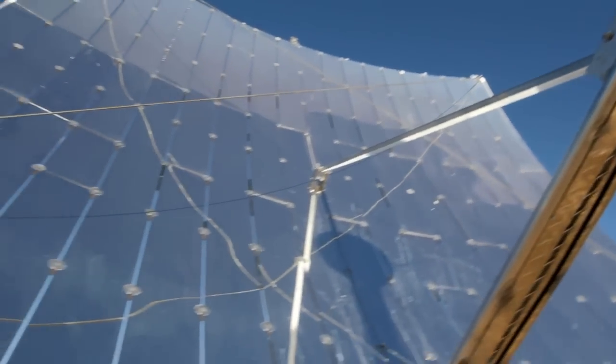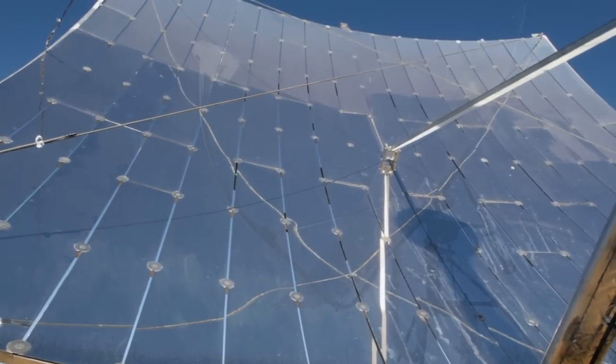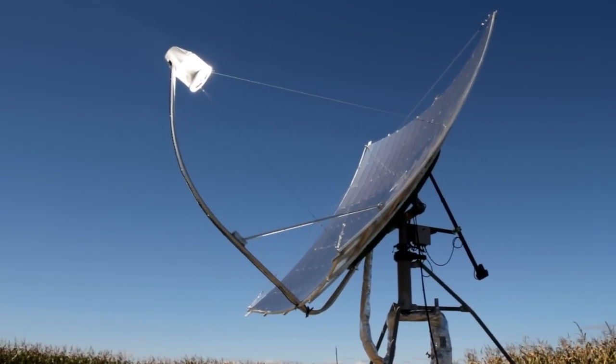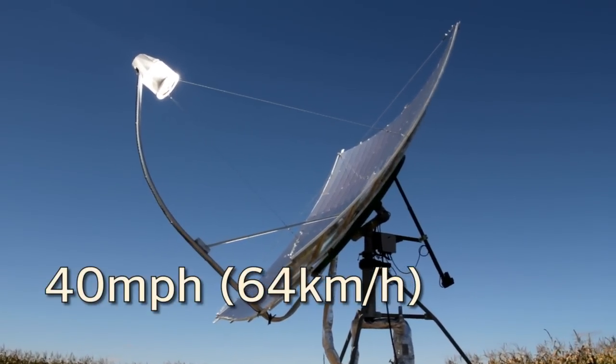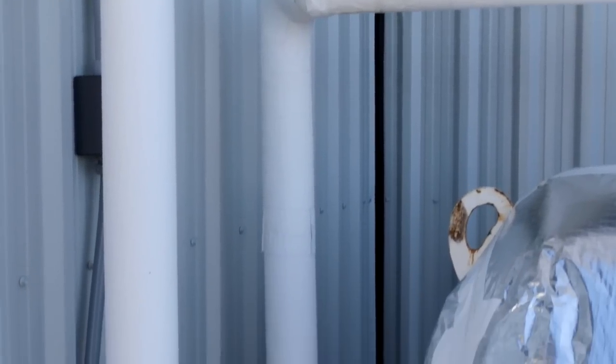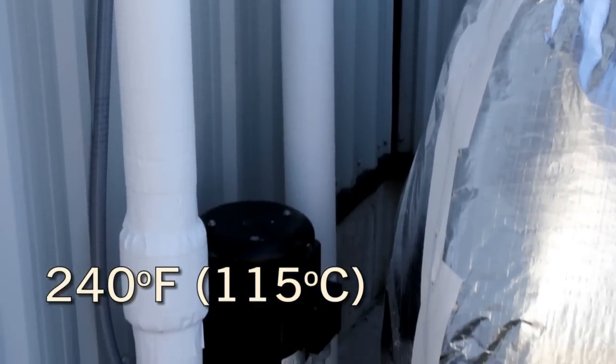There are two diversions in the system which cause the solar dish to shut down and move into a horizontal position: if the monitor registers 40 miles per hour wind, or if the liquid in the holding tank reaches 240 degrees Fahrenheit.